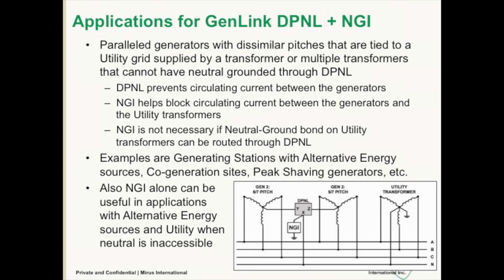Now there are some situations where the DPNL needs to be combined with a neutral grounding inductor. An example might be parallel generators with dissimilar pitch that are tied to a utility grid supplied by a transformer or multiple transformers, but where you do not have access to the transformer's grounded neutral. The DPNL will prevent circulating current between the generators. The NGI is then needed to add some impedance to block the current from the generators to the utility transformers.